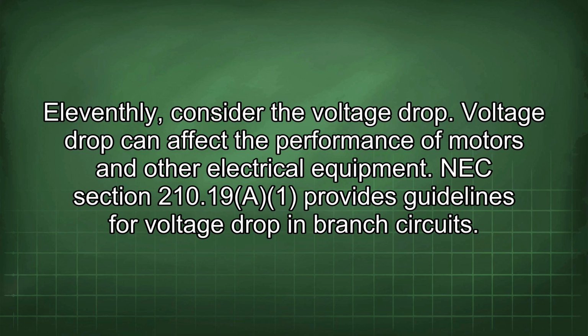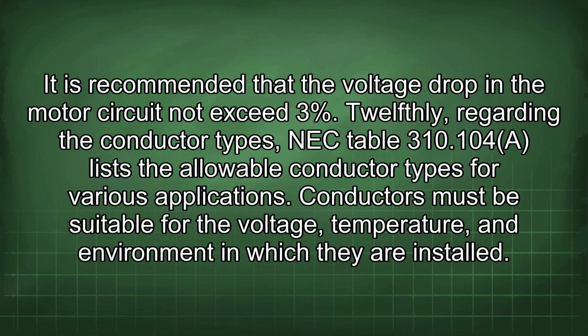11thly, consider the voltage drop. Voltage drop can affect the performance of motors and other electrical equipment. NEC Section 210.19 informational note provides guidelines for voltage drop in branch circuits. It is recommended that the voltage drop in the motor circuit not exceed 3%.